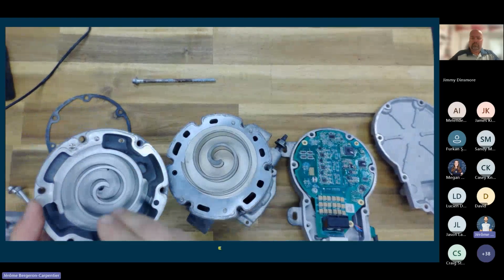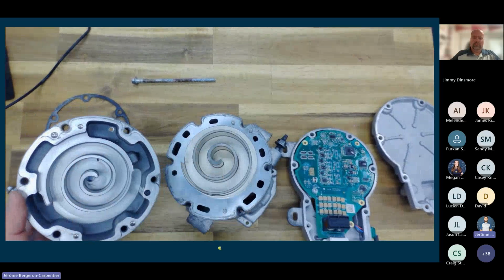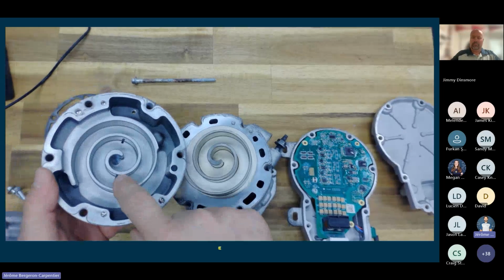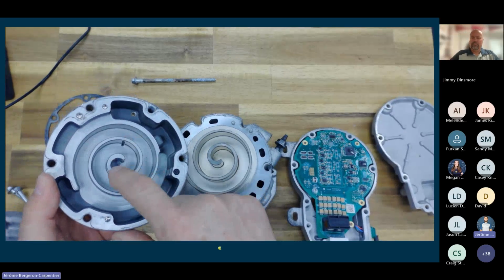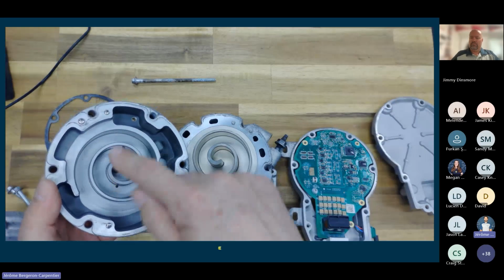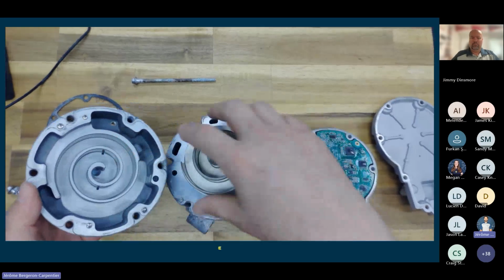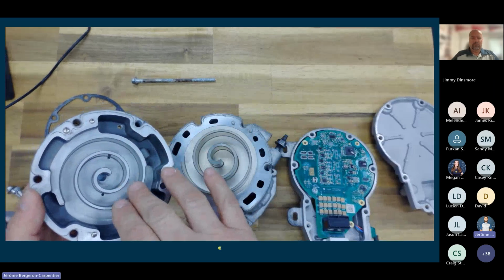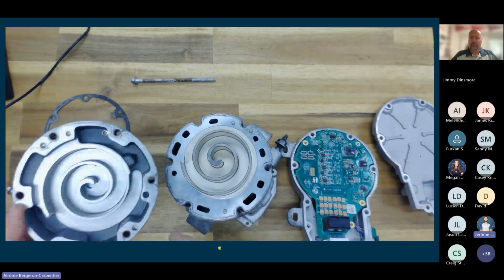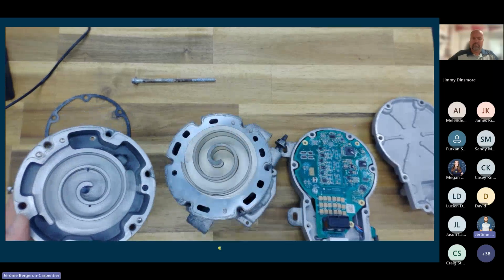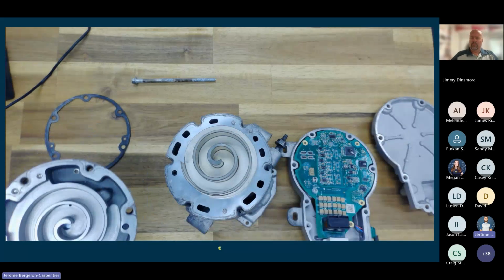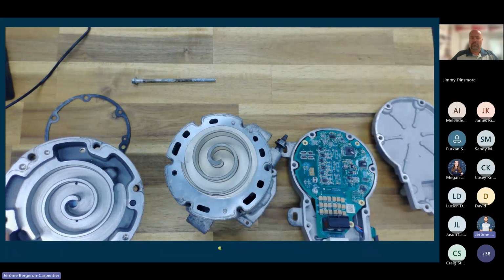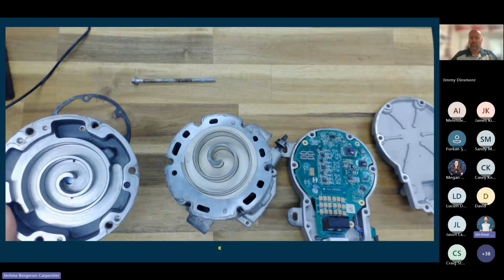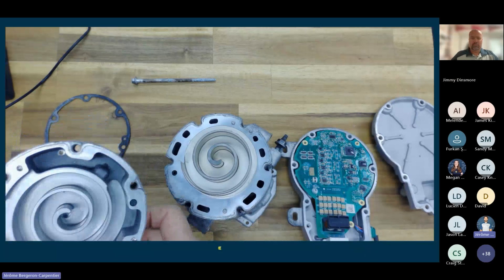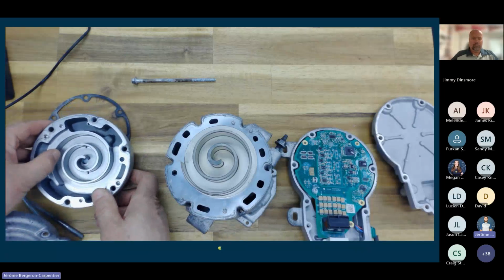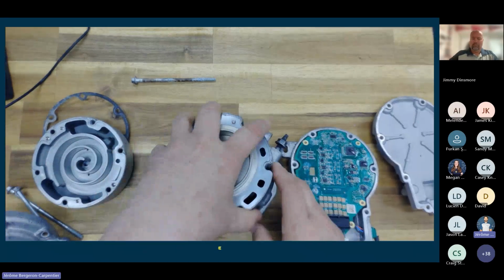It's actually in 90-degree sections. So it's a 4-stage, 4 pressure chambers. You can see the relief in 2 of them there on the outside, and then we have the center one, which is the main discharge. And of course, as we go through the rotation, you get the primary charge or the primary pressure. The reason they do that is to smooth it out. So scroll compressors are typically quiet, easily variable, and very smooth, rather than a piston style or other types of compressors that can be very noisy in the system.